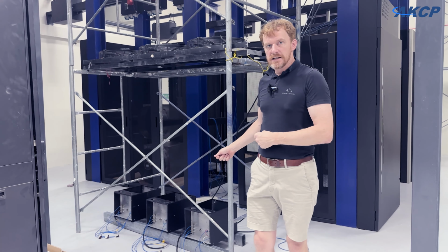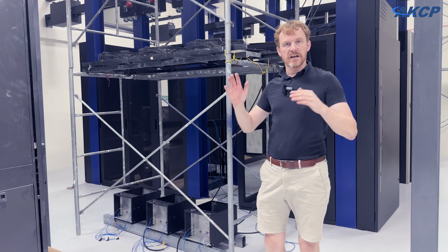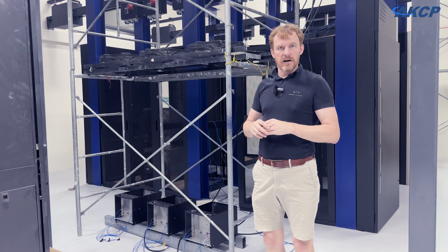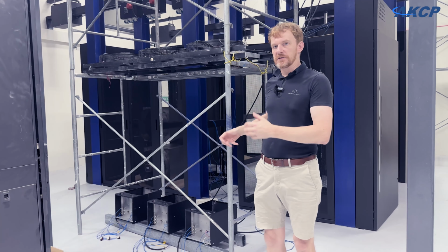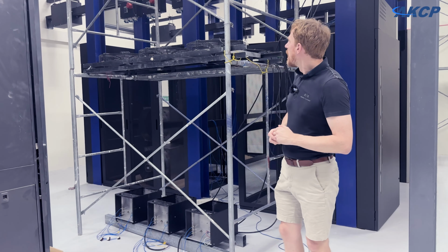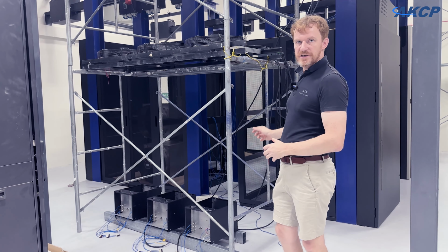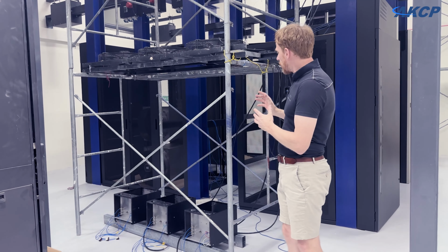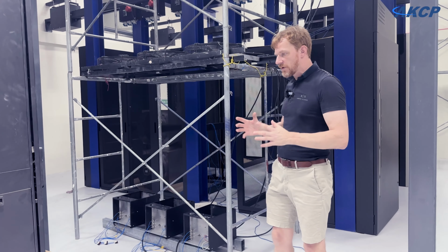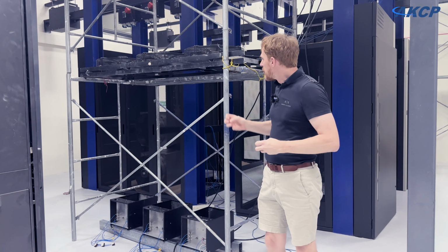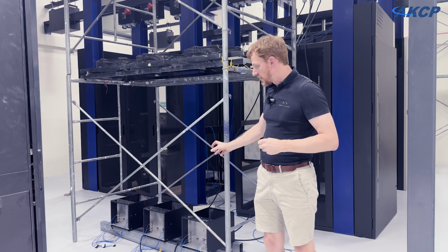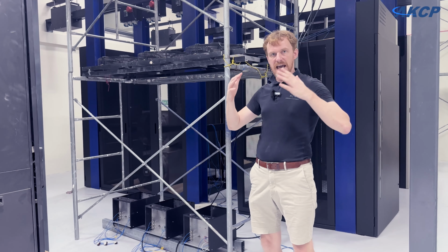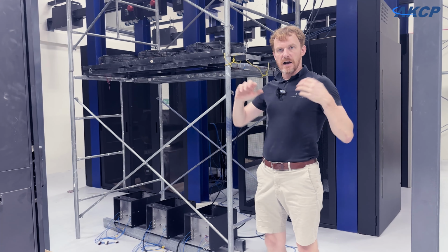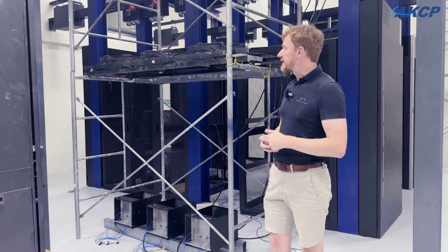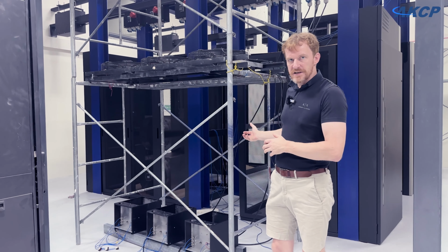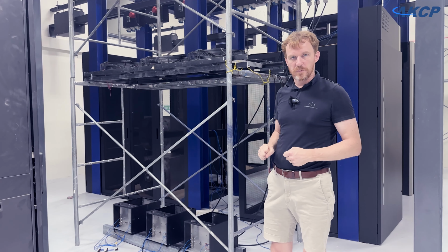We'll also be adding in some relays, so we can also do simulations where we are varying heat loads with the relays randomly turning on and off. That will also help to protect the heaters from overheating. So this current test setup was just to make sure that the bus duct and everything was all working. And then we're going to be getting these mounted inside of the racks. We've got some special enclosures that we've built where the fans mount and also the heaters go, so we can make sure that all of the air is being directed through those heaters and we don't get bypass air. That'll be one of the next things that we need to set up. But for today, we're just making sure now we've got our power connected that everything's working properly and nothing's going bang.